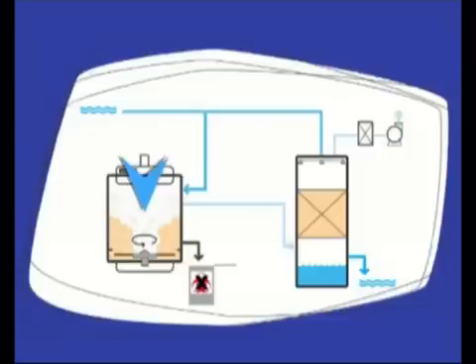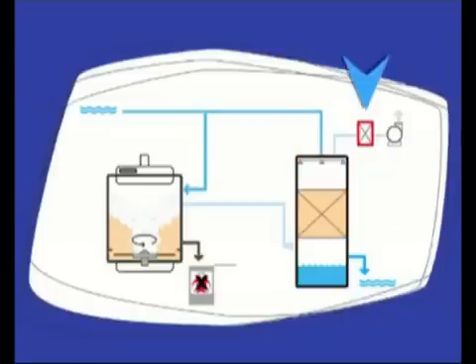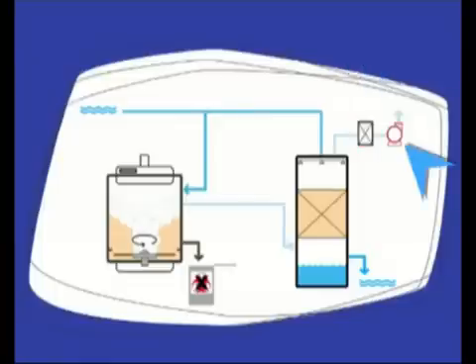A liquid disinfectant is used to sanitize the air tubes at the end of each cycle. A scrubber cleans up smokes and any particles in suspension. A pump maintains the system in constant depression to make it impossible for infected air to escape into the environment. A system filters the outgoing air with an efficacy of 99.999%.